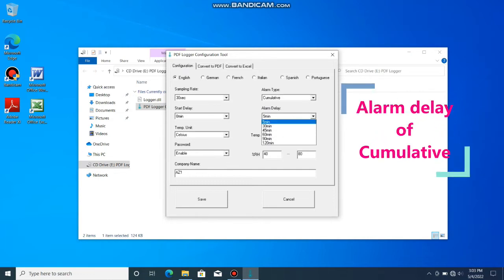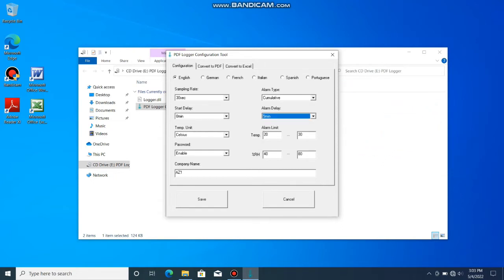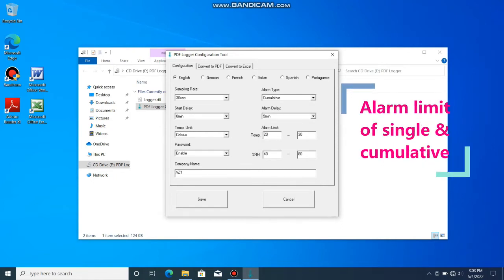Alarm delay: Choose a value between 5 minutes to 2 hours if the alarm mode is cumulative. Alarm limit: The alarm is triggered while the measured value is below the lower threshold or higher than the upper limit.